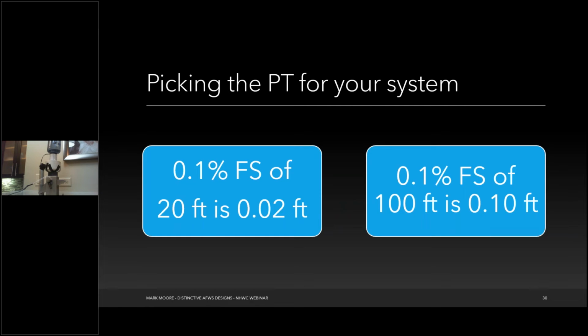So when you're buying your PT, that's usually one of the questions you get asked: what range PT do you want? And you don't necessarily want to pick the biggest range because it's going to give you more error. Alternatively, you don't want a 5-foot PT if the water level can get 20 feet deep because it's not going to work after 5 feet. So you have to pick your middle ground. You want to pick something that covers the full range of your system, but also is low enough that you don't get a very high error.